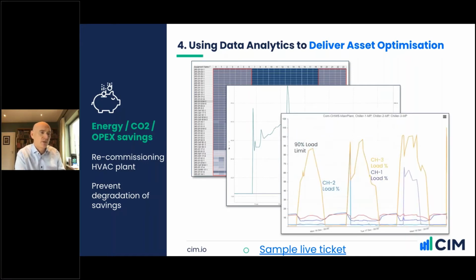And the last one talks about balancing the run hours between chillers. You can see in this instance the yellow line here is one chiller, and when it goes up to a 90% load, it starts to go outside its efficiency band. So the objective, and what we did, was distribute the load better amongst the 3 chillers and allow them to individually operate at higher efficiencies, which increased the overall COP.